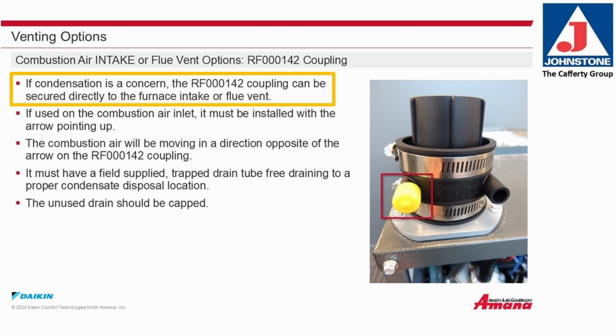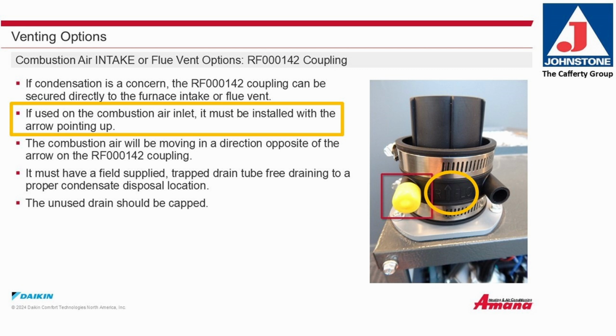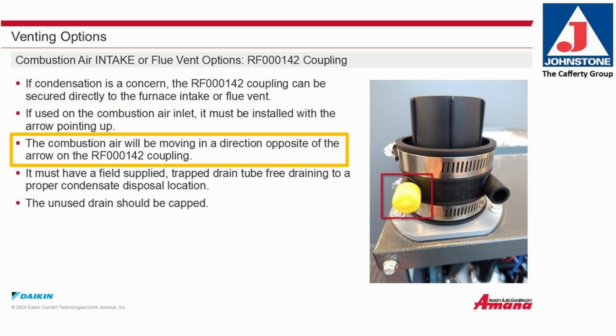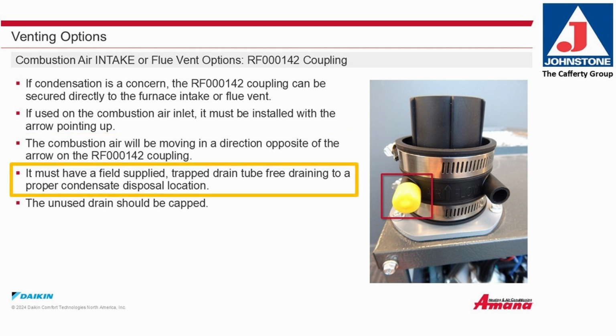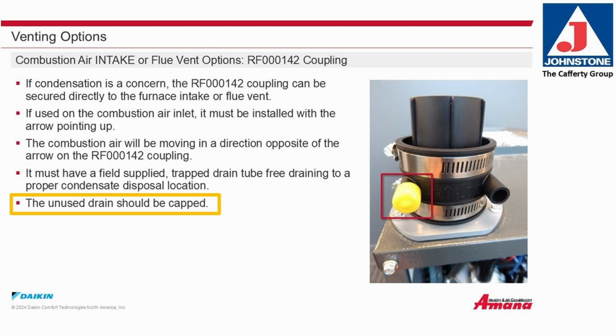If condensation is a concern, the RF000142 coupling can be secured directly to the furnace intake or flue vent. If used on a combustion air inlet, it must be installed with the arrow pointing up. The combustion air will be moving in a direction opposite the arrow on the RF000142 coupling. It must have a field-supplied, trapped drain tube, free draining to a proper condensate disposal location. The unused drain should be capped.